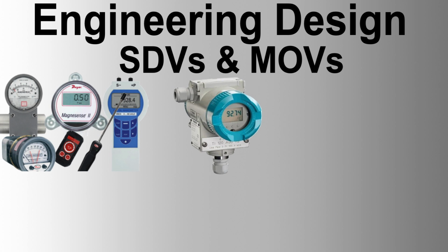The actuator shall be directly mounted on the valve and include the motor, actuator unit, gears, local mechanical position indicators, phase discriminator, integral limit switches, hand wheel, and electrical starter control as a self-contained unit. The actuators shall be designed for output torques at least 250% of the valve design torque. Operating speed shall be specified on the vendor data sheets.